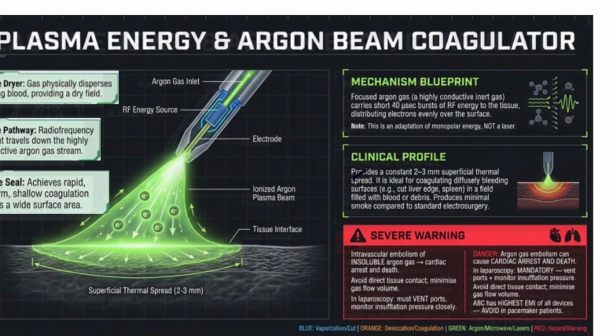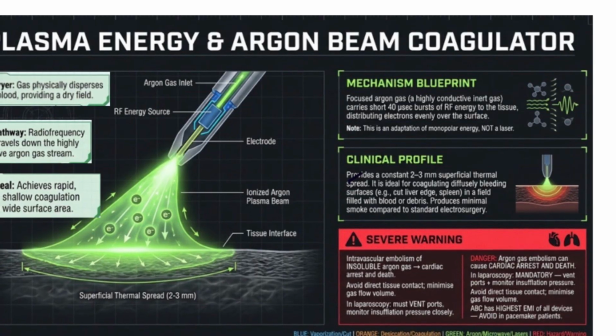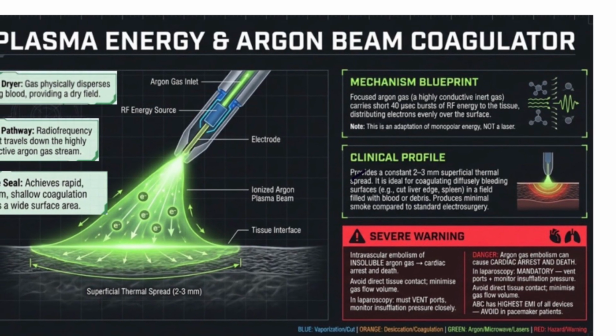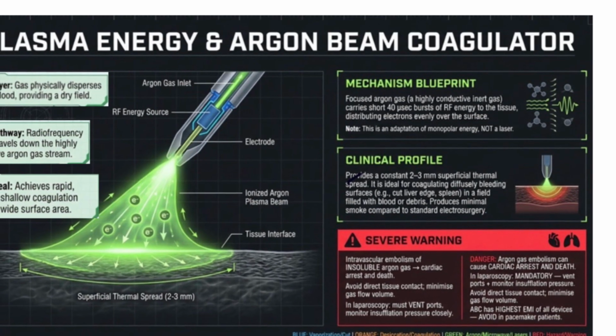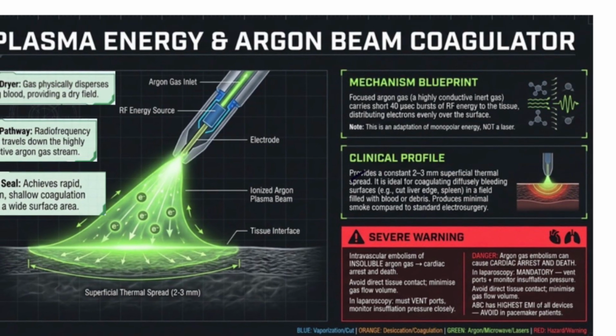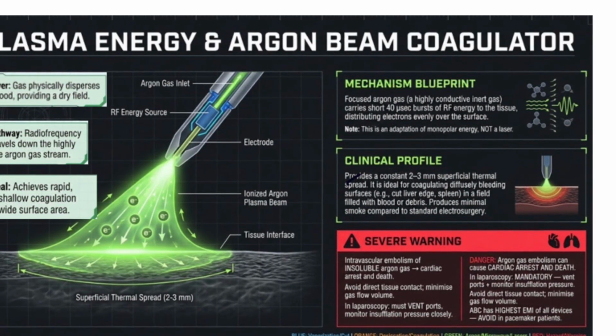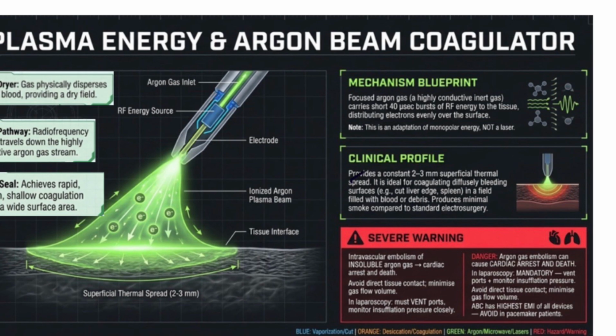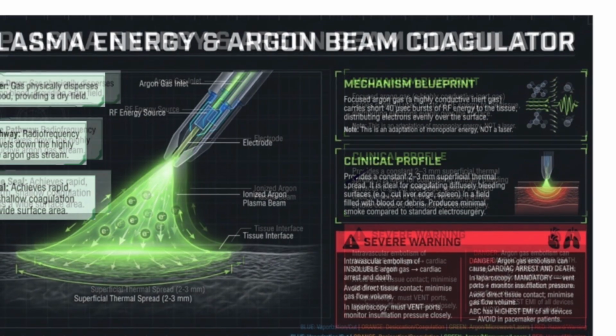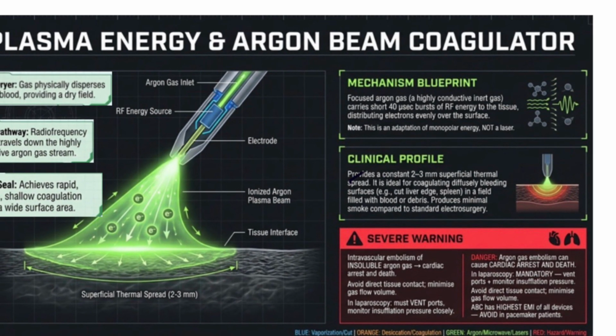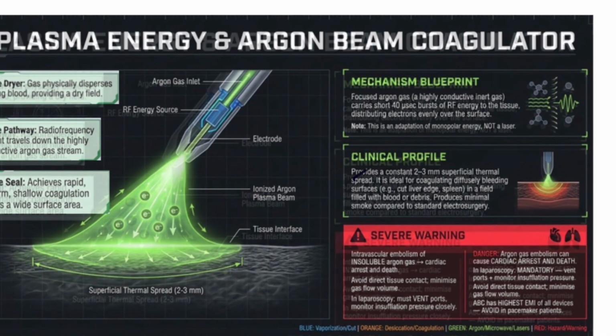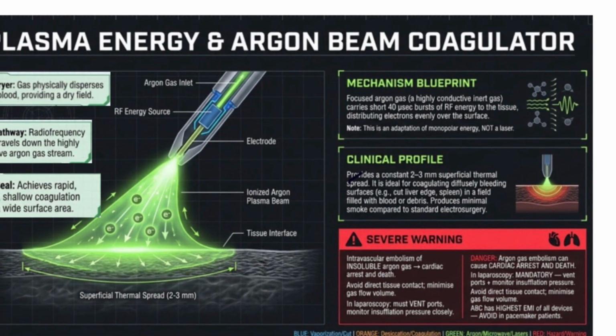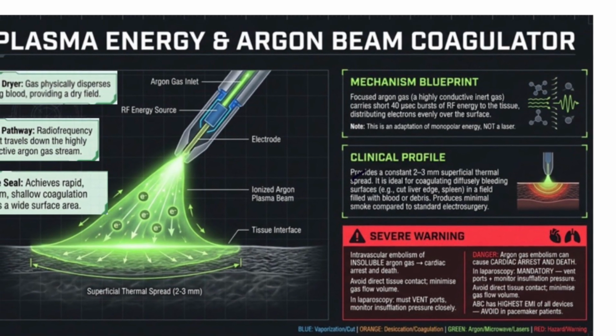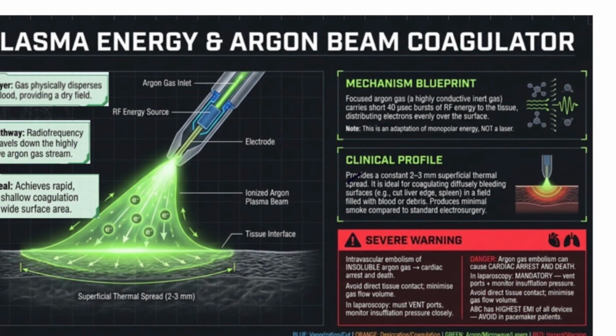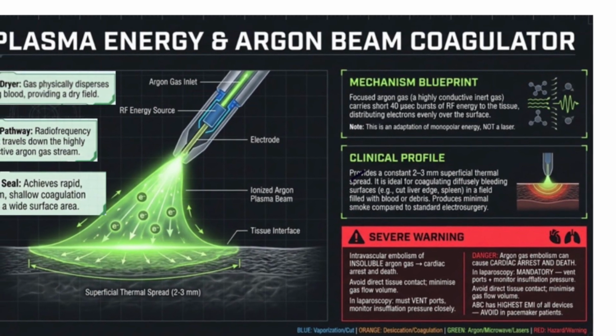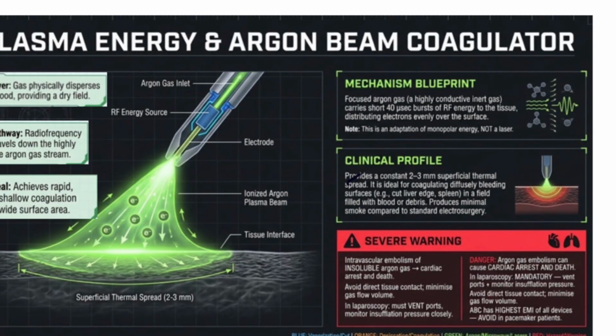Avoid direct tissue contact and minimize gas flow volume. In laparoscopy, vent the ports and monitor insufflation pressure closely. The danger is argon gas embolism, which can cause cardiac arrest and death. In laparoscopy, it is mandatory to vent the ports and monitor the insufflation pressure. Avoid tissue contact and minimize gas flow volume.